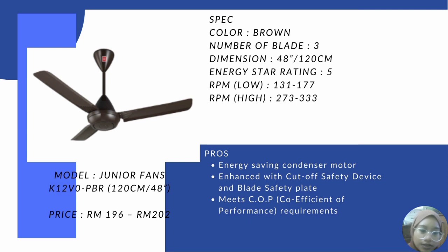The RPM high is 273 until 333. The reason why we choose this fan is that it has an energy saving condenser motor. It is also enhanced with a cut off safety device and blade safety plate, and it meets the COP, or coefficient of performance, requirement.